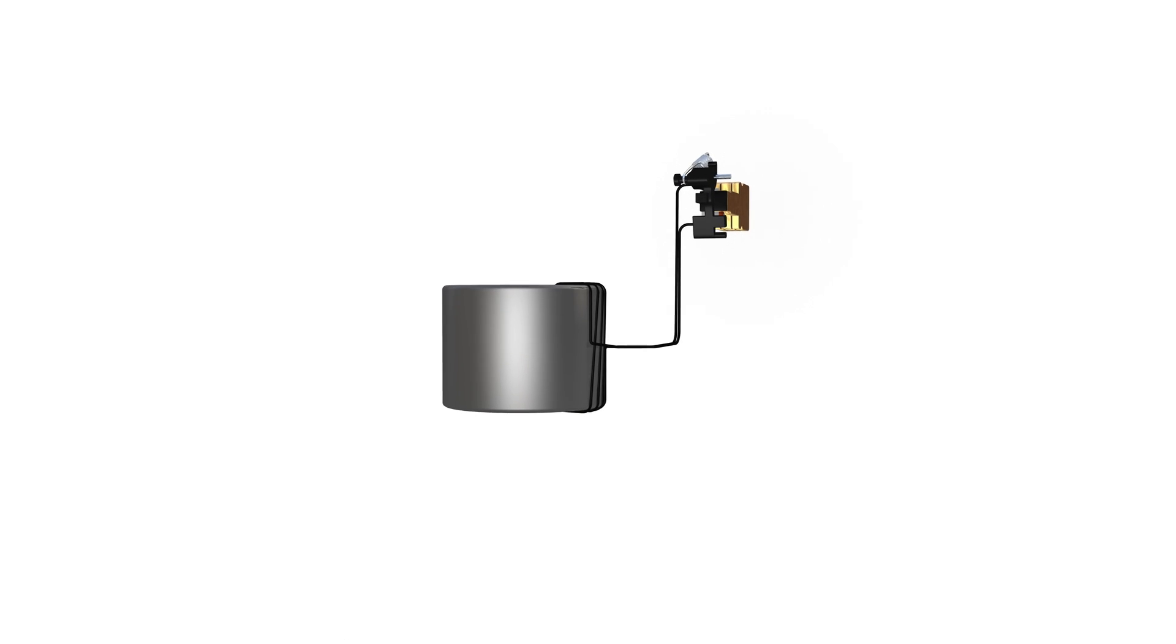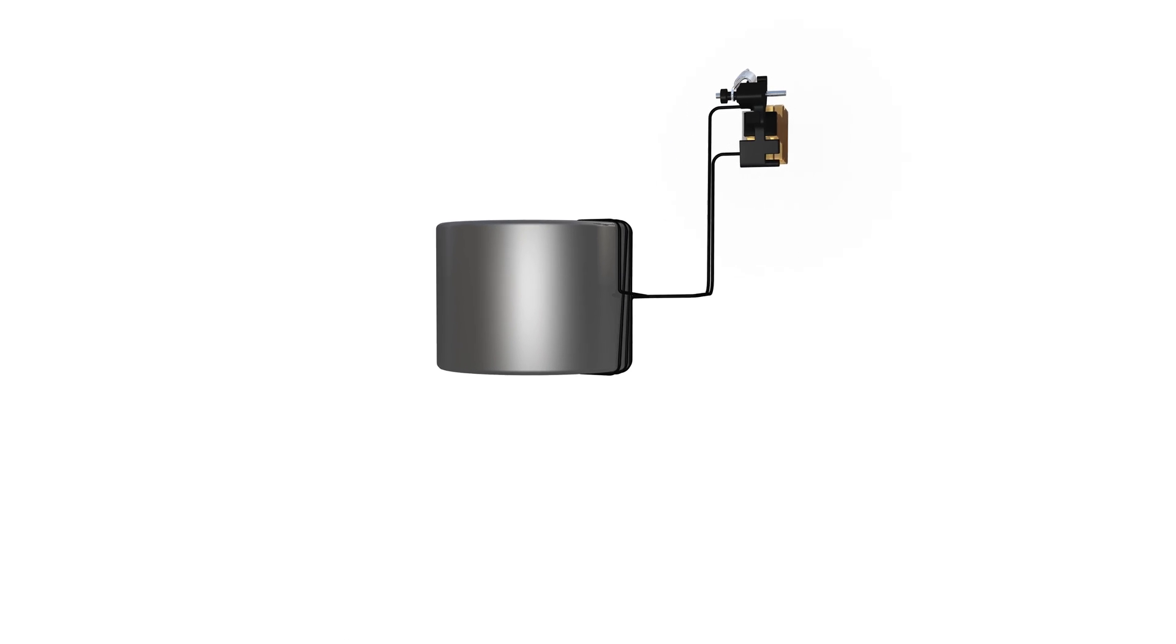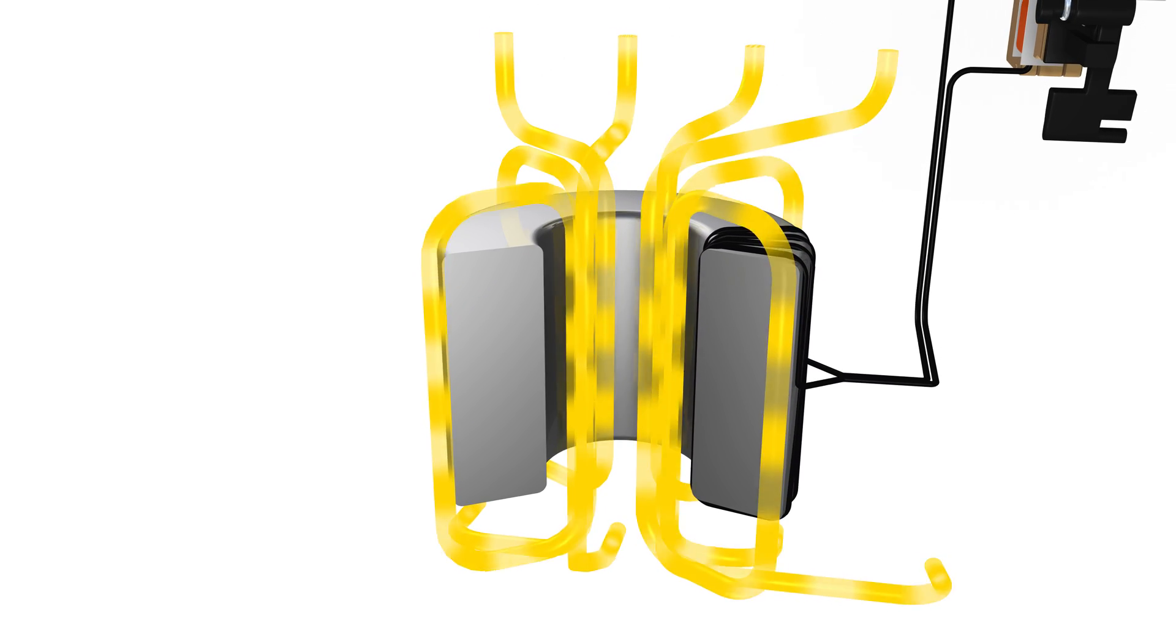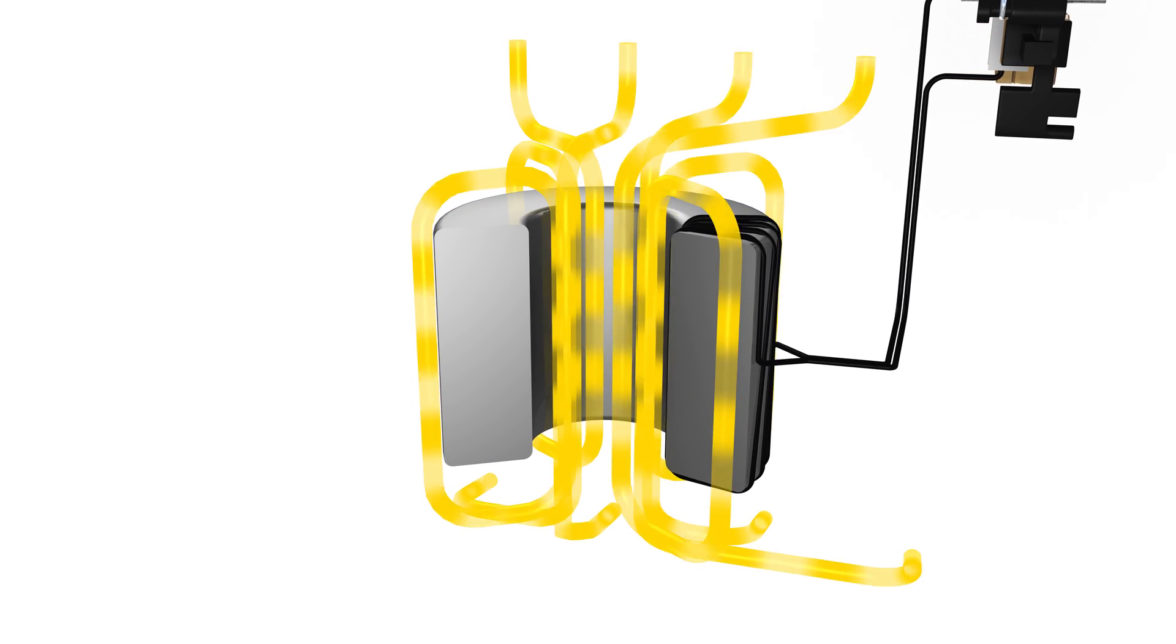The current flows through the summation current transformer in the RCCB. In a fault-free system, the magnetic fields generated by the live conductors cancel each other out. Thus, there is no residual magnetic field to induce a voltage on the transformer secondary winding.